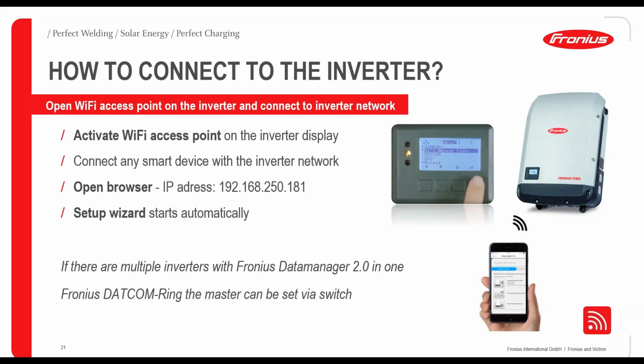Therefore, you have to activate the Wi-Fi access points, which can also be done on the inverter, very easy. Then the inverter opens its own network. You can connect with any mobile device, whether it's a smartphone or a laptop. Connect to the inverter and then just do 2 setup wizards. There is the technician wizard and the SolarWeb wizard, which can be very easily done within, I would say, 5 minutes. And the initial commissioning is completed, and it's about to run, and you have got the full system in the Fronius SolarWeb, and it's fully commissioned.